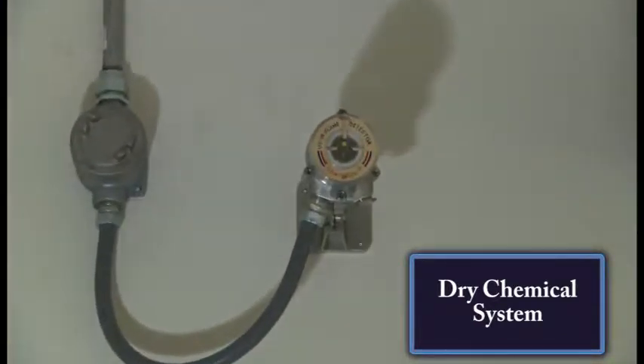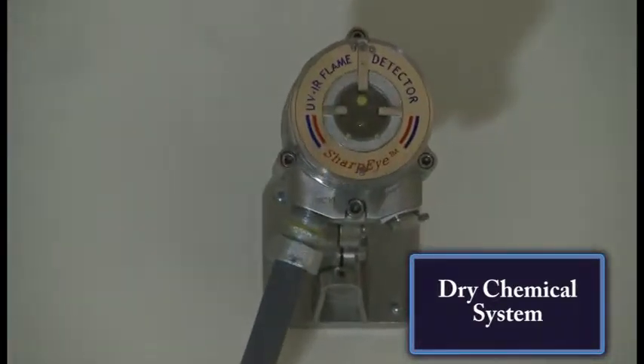Activation of any heat detector or electronic release station will cause the following to occur. The alarm detector's red status light will illuminate. The device's custom address will be displayed on the control panel's LCD display located outside the room. The horn strobe will operate. The HVAC systems in the building will shut down. The 10-second programmed pre-discharge time delay will begin. Upon the expiration of the 10-second delay, a discharge condition will be annunciated on the control panel. The dry chemical suppression system will discharge.